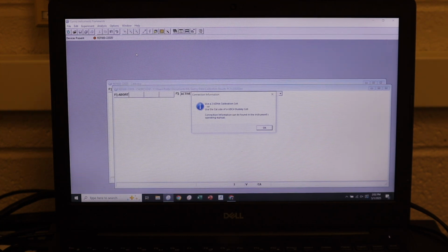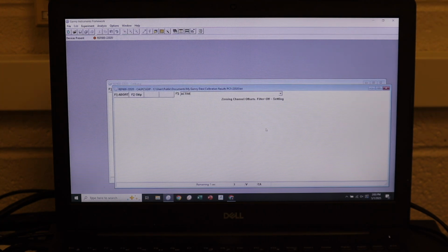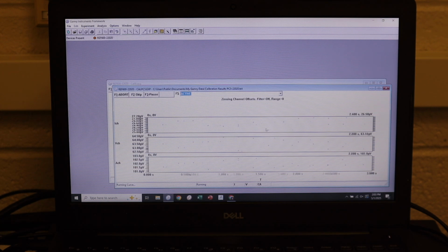It's asking us to connect a 2 kilo ohm calibration cell or a dummy cell, so we can go ahead and hit OK to that. Then it's asking us one more time to make sure that the unit is warmed up, which in our case it is. So we can go ahead and hit OK, and it should begin to run that experiment now. Now we're calibrating essentially the potentiostat and making sure that the Gamry will be ready to be used, either because we moved it to a new location, or just because it has been a long time, or potentially there are discontinuities in your measurement stemming from the system not being in equilibrium, or whatever the reason.